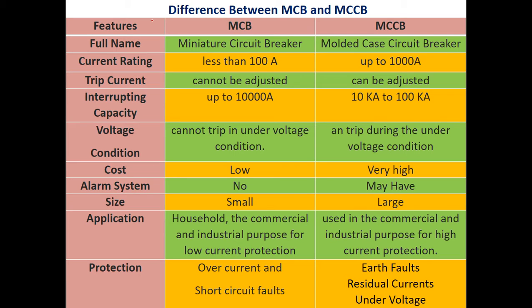On the basis of these features tabulated here, we will discuss the differences between MCB and MCCB. The full name of MCB is miniature circuit breaker, whereas MCCB stands for molded case circuit breaker. Regarding current rating, MCB is a low current rating device, of order less than 100 amperes, whereas MCCB is a high current rating device, rated up to 1000 amperes.